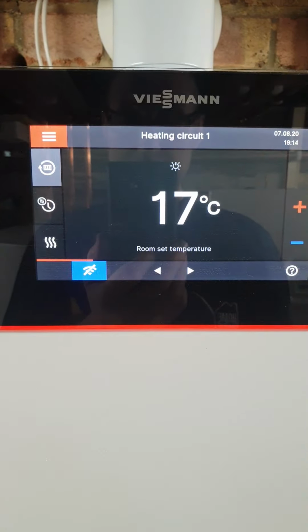That's it. Our new function on this boiler that's a bit different to the old ones, for people who haven't fitted that many of these, is that before, if you had the weather comp set and you'd set the temperature for say 21, if the outside temperature rose above 22, it just switched everything off, switched off the heating, switched off the pumps and everything. But that function's been replaced and now it's preset to 25. So irrelevant of what temperature it is, if it's over 25 outside, the boiler switches into standby mode.